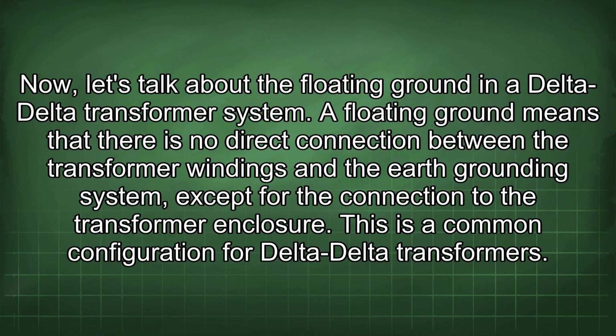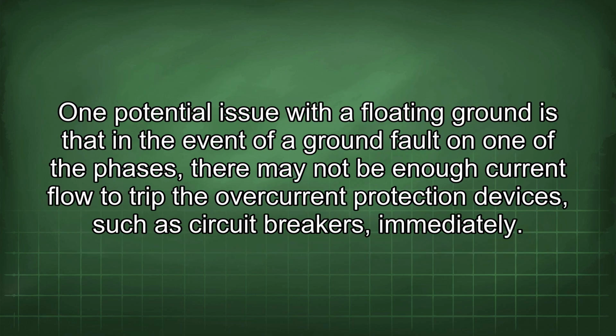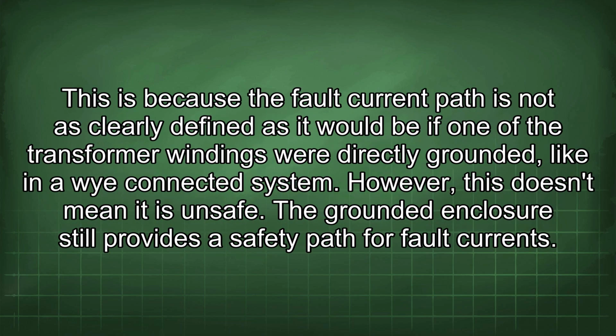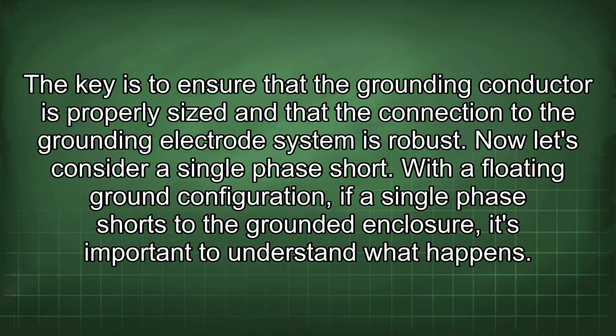A floating ground means that there is no direct connection between the transformer windings and the earth grounding system except for the connection to the transformer enclosure. This is a common configuration for delta-delta transformers. One potential issue with a floating ground is that in the event of a ground fault on one of the phases, there may not be enough current flow to trip the overcurrent protection devices, such as circuit breakers, immediately. This is because the fault current path is not as clearly defined as it would be if one of the transformer windings were directly grounded, like in a Y-connected system. However, this doesn't mean it is unsafe. The grounded enclosure still provides a safety path for fault currents. The key is to ensure that the grounding conductor is properly sized and that the connection to the grounding electrode system is robust.